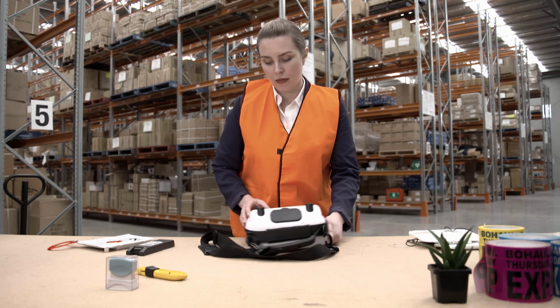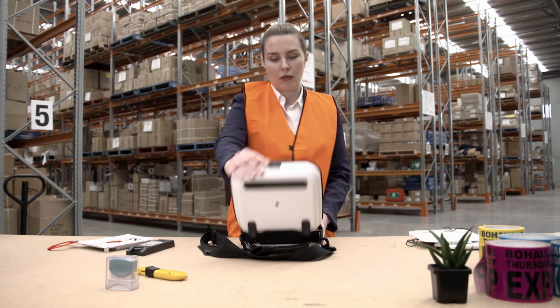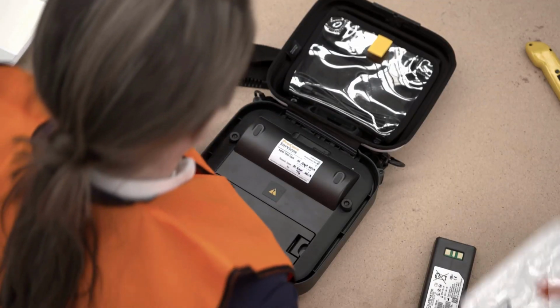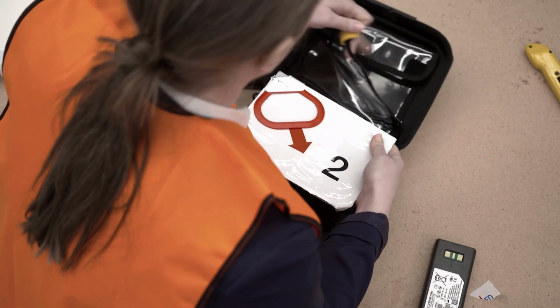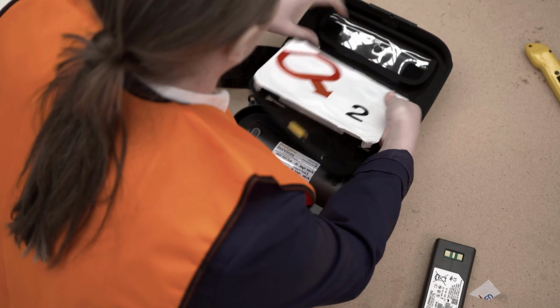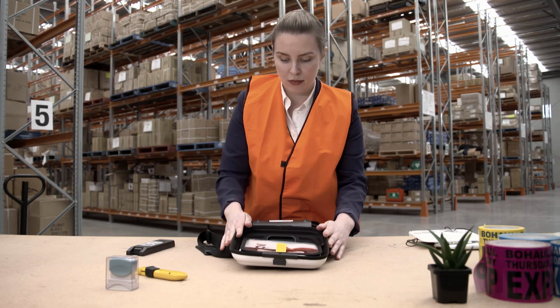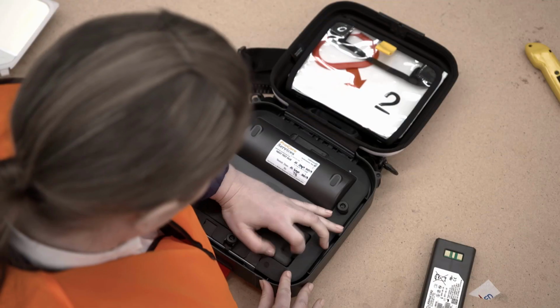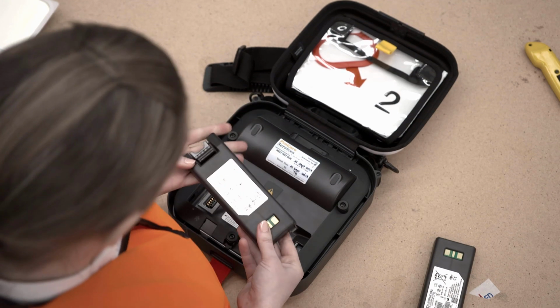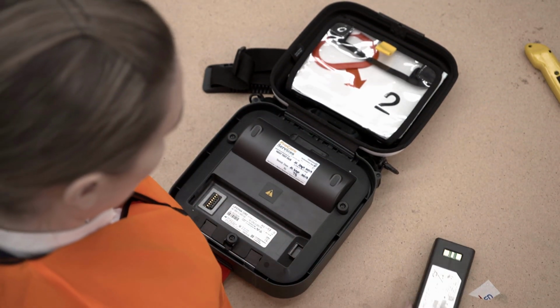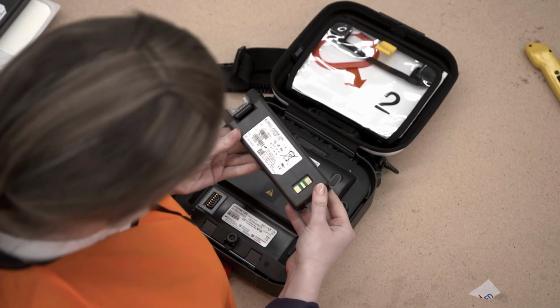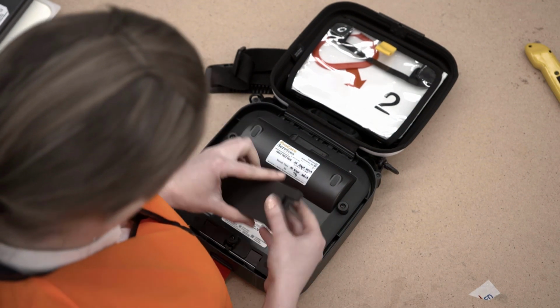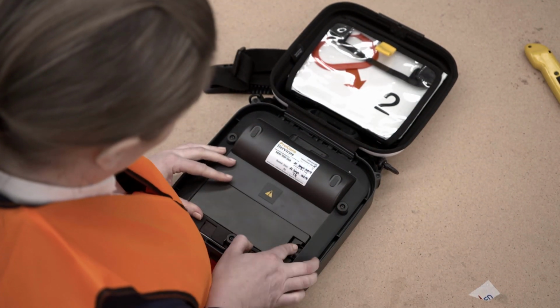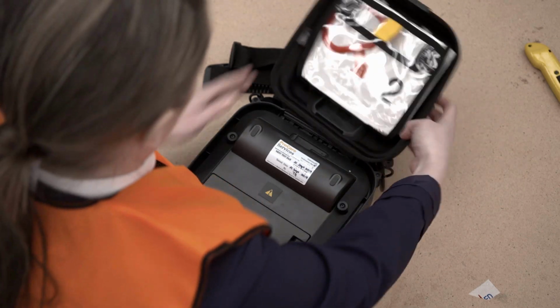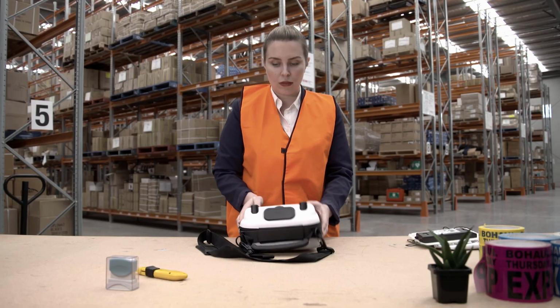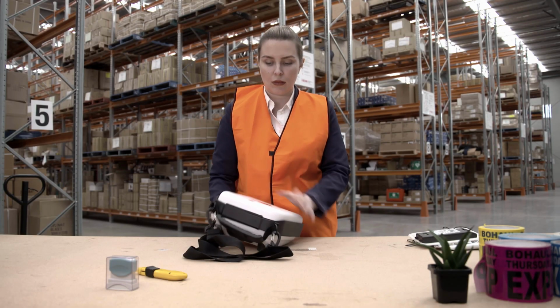Turn the defibrillator over and open the back lid of the device. You can store a spare pad pack in the back of the device. To change the battery, press the locking tab on the battery and remove from the device. Check the manufacture date on the new battery and click into place. Close the back lid of the defibrillator and turn the device over to the front.